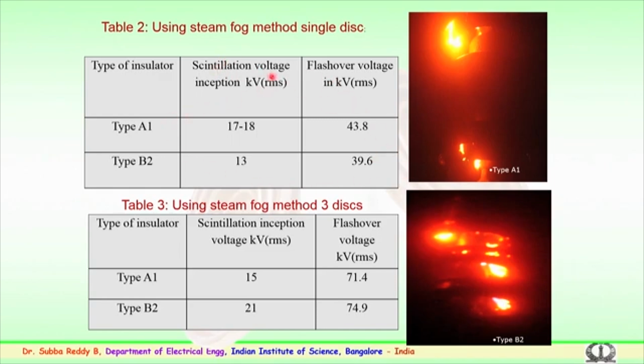For each type, at least 3 discs of the same dimensions were used for the experiments. Similarly, using the steam fog, 3 discs in a string were also tested. You can see the scintillation inception is early in comparison to the single disc, and the flashover voltage is 71 kV, whereas for the single disc it is 43 kV. When you put 3 discs, it is not a linear phenomenon where you see a proportional increase of the flashover voltage.